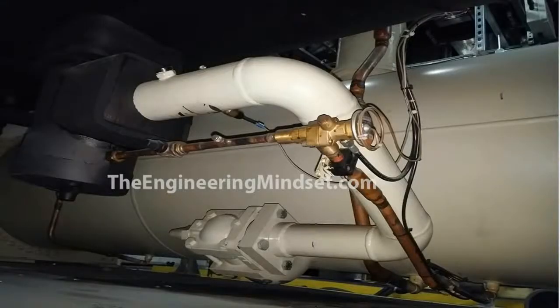So the first expansion valve we're going to look at is the pilot operated thermal expansion valve. In the real world, the pilot operated thermal expansion valve will look something like this. Here we've got the pilot expansion valve located just here, and over here we've got the main thermal expansion valve. Now the refrigerant will flow from the condenser. This is the condenser here, and the refrigerant will flow into this. This is a king valve, just so you can isolate it and you can lock that off. So it will flow through this valve, up through this tube and into the base of the main expansion valve, and then up into the evaporator.